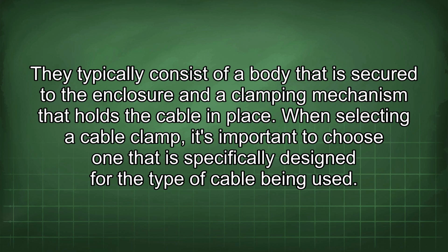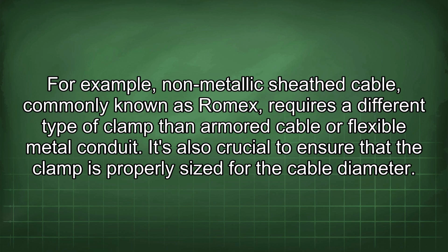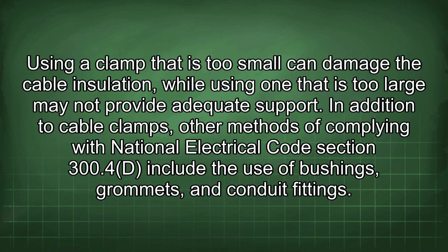They typically consist of a body that is secured to the enclosure and a clamping mechanism that holds the cable in place. When selecting a cable clamp, it's important to choose one that is specifically designed for the type of cable being used. For example, non-metallic sheath cable, commonly known as Romex, requires a different type of clamp than armored cable or flexible metal conduit. It's also crucial to ensure that the clamp is properly sized for the cable diameter. Using a clamp that is too small can damage the cable insulation, while using one that is too large may not provide adequate support.